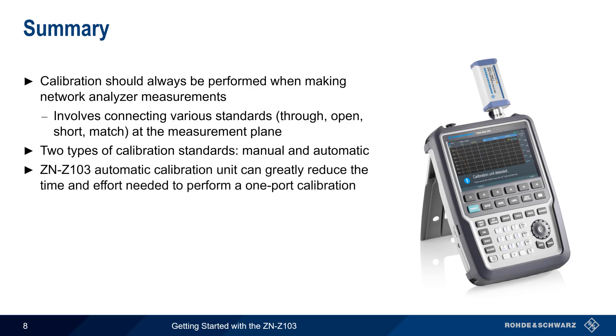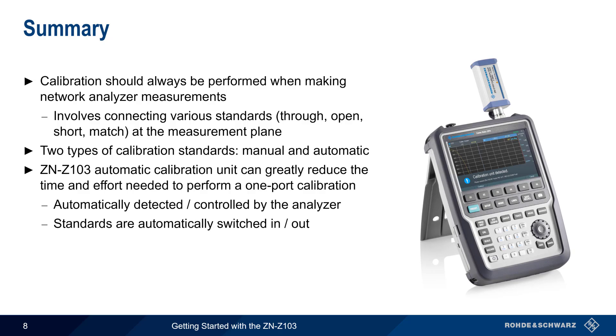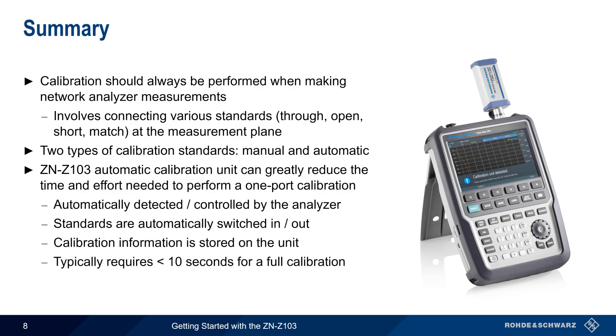The Rohde & Schwarz ZN-Z103 automatic calibration unit is supported by many Rohde & Schwarz VNAs and can greatly reduce the time and effort needed to perform a one-port calibration. The unit is automatically detected and controlled by the analyzer over a USB connection, with the standards being automatically switched in and out by the analyzer as needed. Calibration information is stored on the ZN-Z103 and is read out automatically by the analyzer as well. In most cases, calibration takes less than 10 seconds, and is therefore substantially faster than a manual calibration.